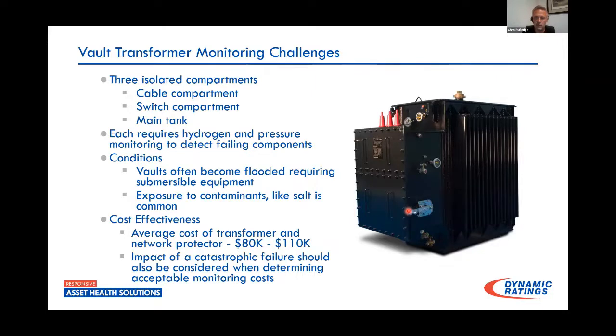And then you have a switching compartment, which is this switch, which will allow you to ground A phase, B phase, or all 3 phases of the transformer when it is out of service for maintenance and testing purposes. This compartment goes up behind the cable compartment, and there are bushings that feed through here, and then bushings from the switch into this main tank back here, which is where our coil and core are contained. So that's the 3 compartments we're talking about.